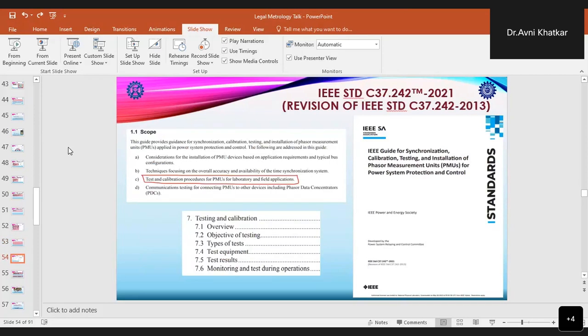IEEE also issued a guideline for the synchronization, calibration, testing and installation of PMUs for power system protection and control. This is IEEE standard C37.242/2021. It is the revision of the 2013 standard, and it provides the guidance which is required for the test and calibration procedures for PMUs for the laboratories and their field applications.